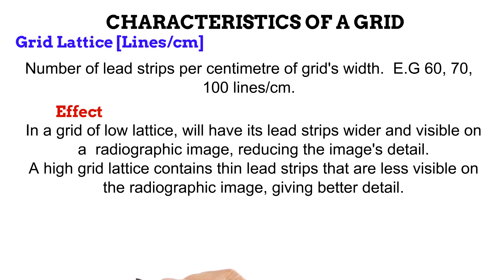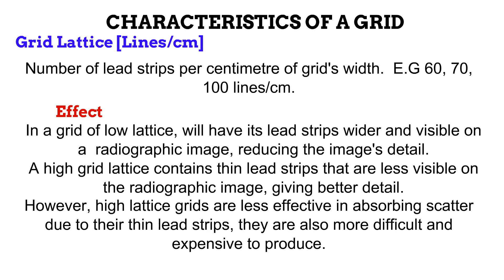On the other hand, a grid with high lattice has thinner lead strips that are less visible on the image, giving it better detail. However, the thin strips of high lattice grids make them less efficient at absorbing scattered photons, and some scatter bypasses these thinner strips. Another disadvantage of high lattice grids is that they are more difficult to produce, making them more expensive.